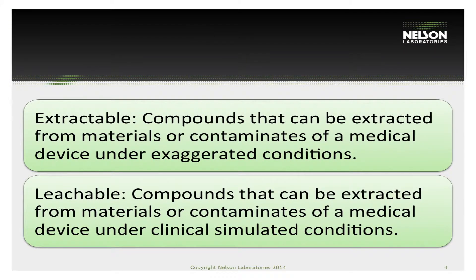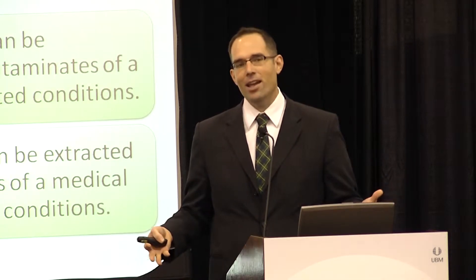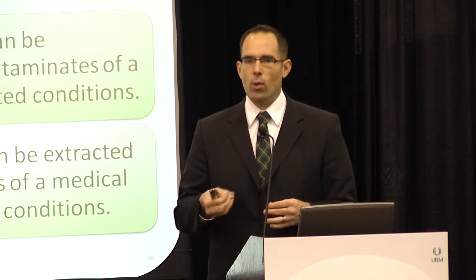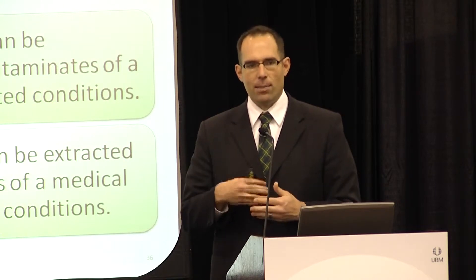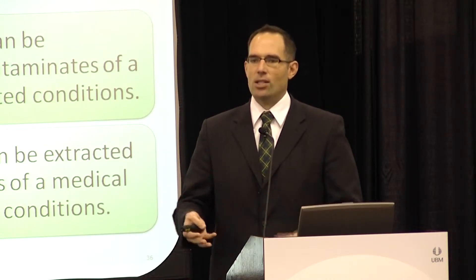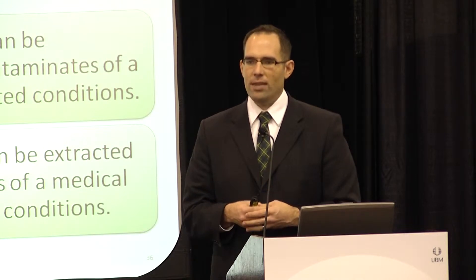You do have to be careful with extractables — you can go way overboard and actually melt the plastic down into a liquid. What useful data are you going to get out of that unless your end purpose is to dissolve everything? When looking at leachables, you really want to see what comes off a medical device that would impact the patient — what chemicals are coming off that are toxicologically concerning.